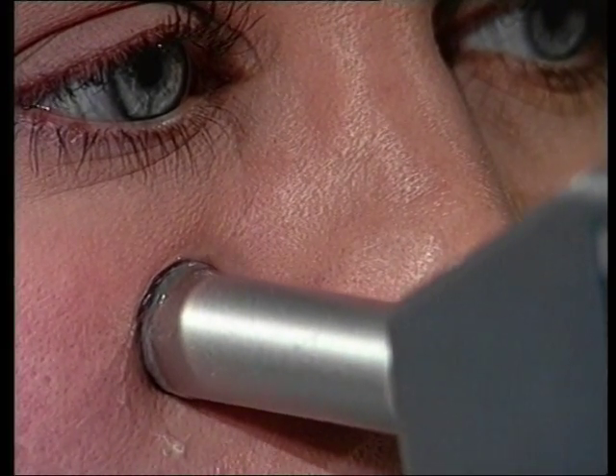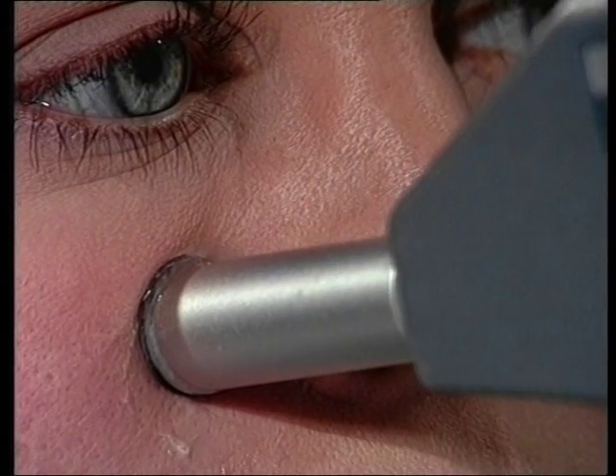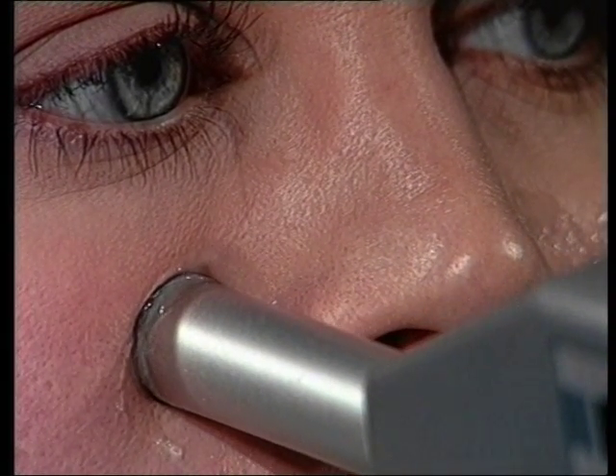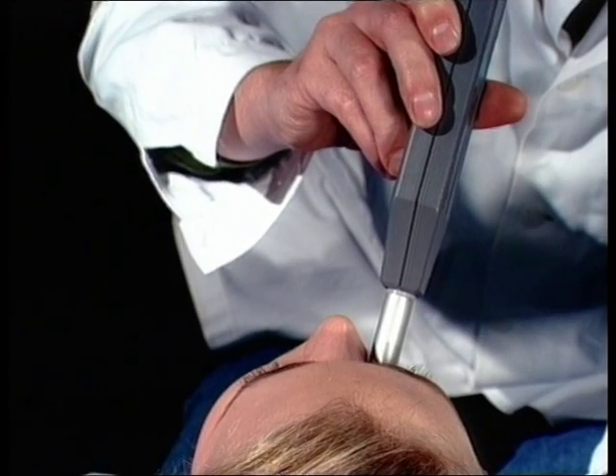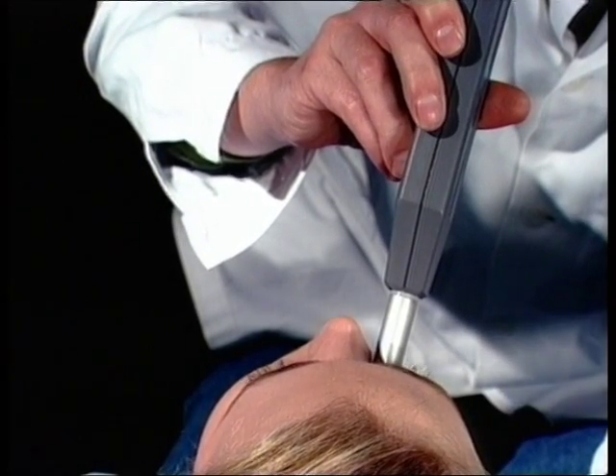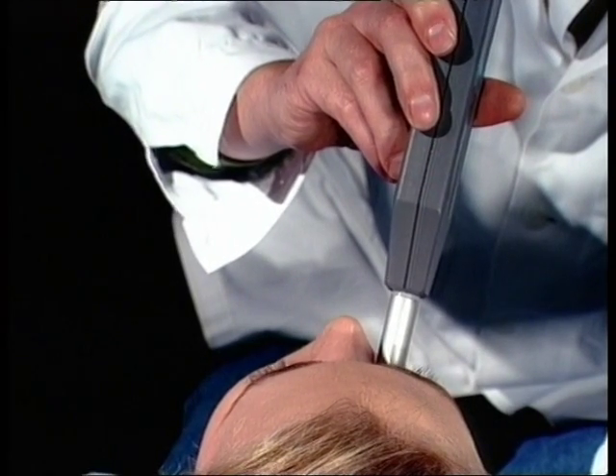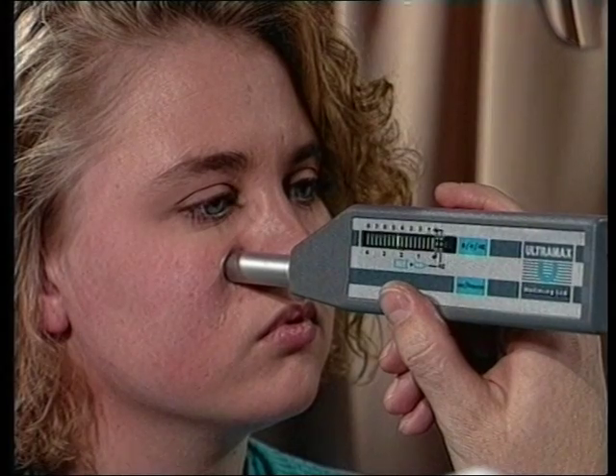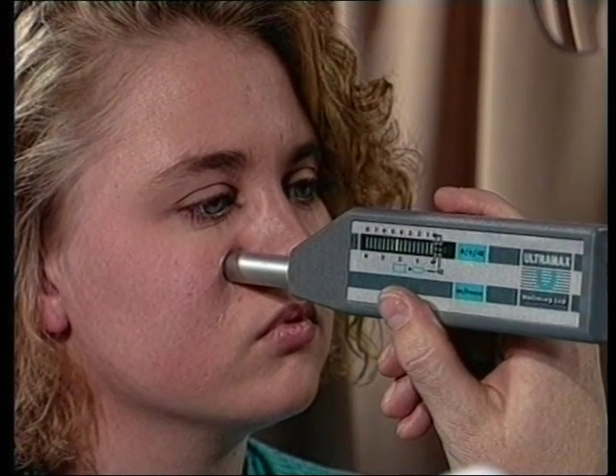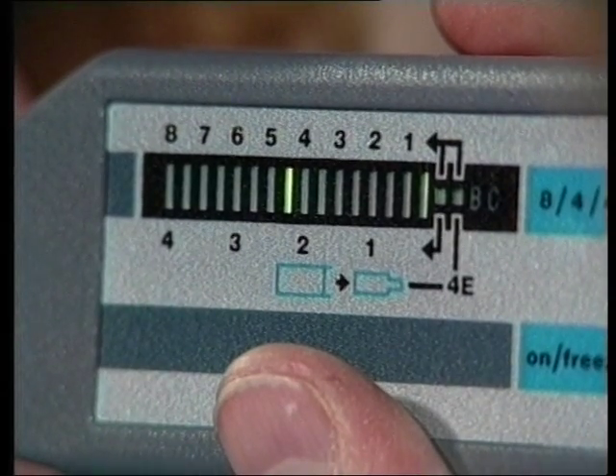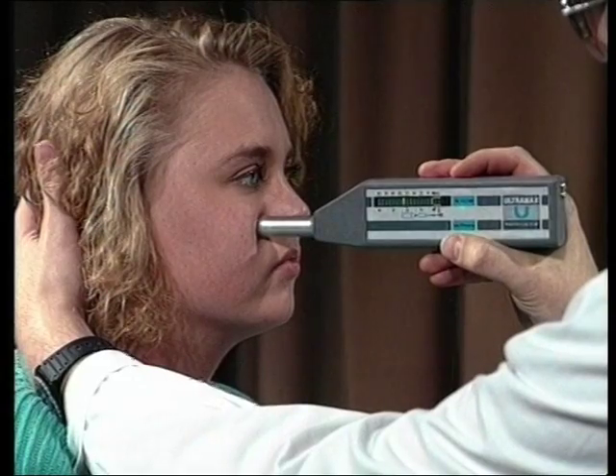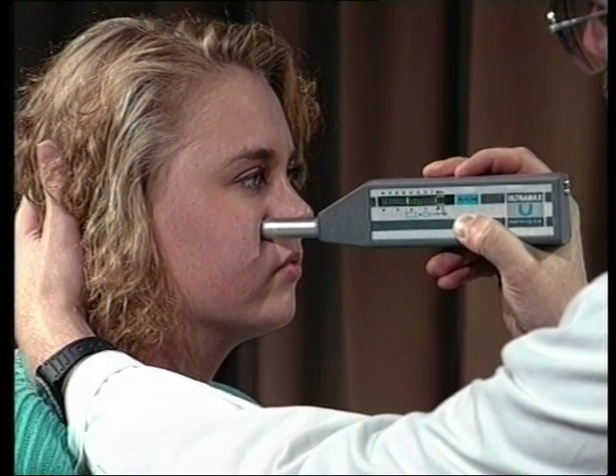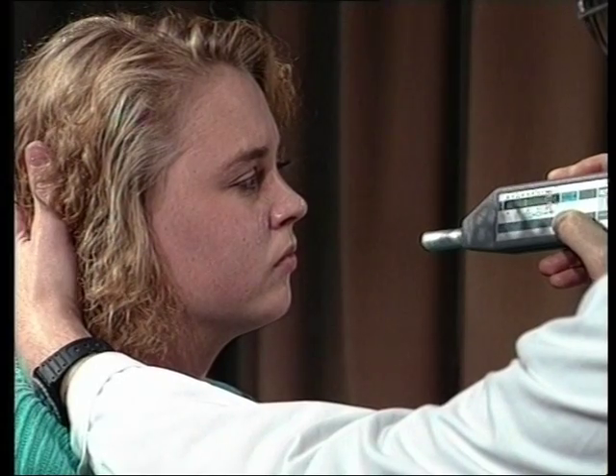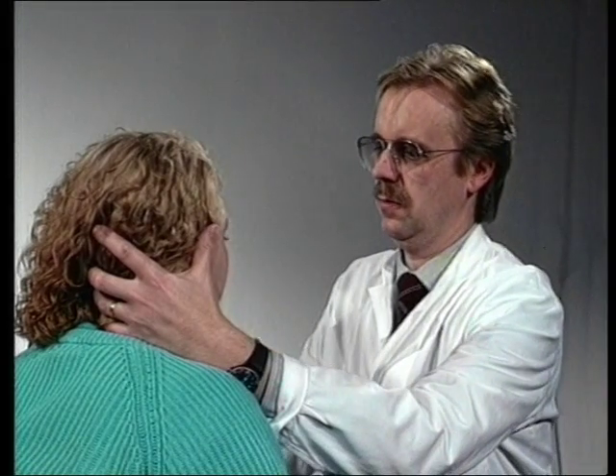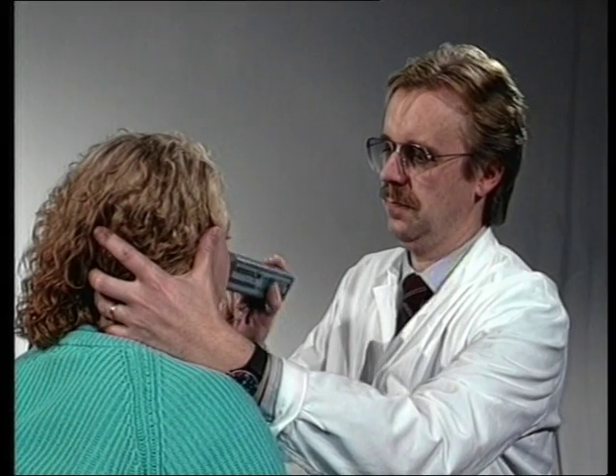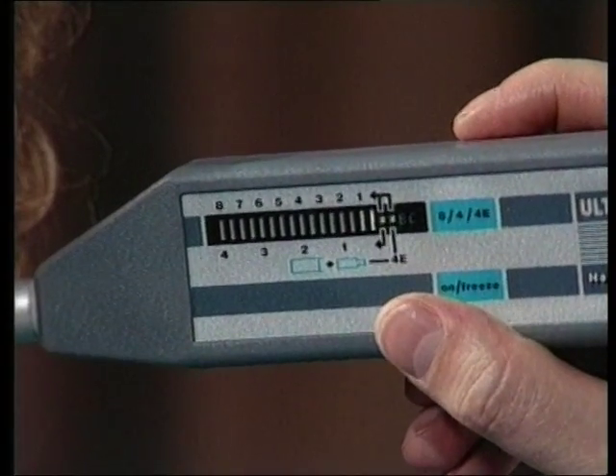Whilst keeping the tip of the probe still, the device is swiveled in search of a back wall echo. In most cases, the best reflections are found by pointing the probe in a slightly medial direction. A back wall echo indicates a sinus with retained exudate. A back wall echo is always preceded by an echoless region on the display. The findings may be shown to the patient by pushing the freeze button and by keeping it depressed. The cavity is free from exudate if during thorough examination only an anterior wall echo is encountered.